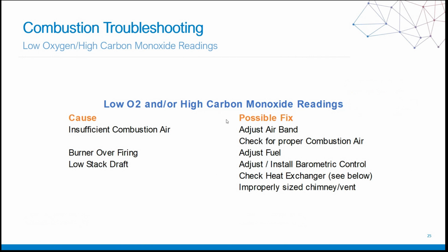So we want to check for proper combustion air. We have a burner that is overfiring. Again, one of the things that we want to check is fuel. Is the gas pressure too high?